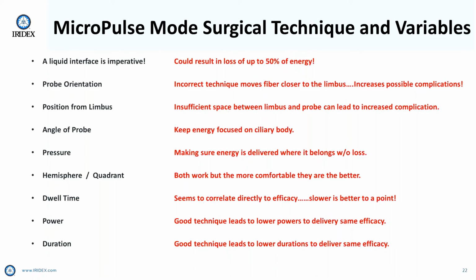Angle of the probe. By angling the probe towards the center of the globe, we keep the energy focused on the ciliary body and away from tissues that we do not want to treat. Pressure. By applying adequate pressure, much like a writing instrument, we are making sure that the energy is delivered where it belongs without loss. Technique. Looking at hemispheres versus quadrant, both work, but the more comfortable you are in its utilization, the better your treatment will be. So if you're more comfortable doing 3 clock hours because exposure is better, that is fine. If you're more comfortable doing 6 clock hours and a hemispheric approach, that is fine as well. They both lead to good efficacy.